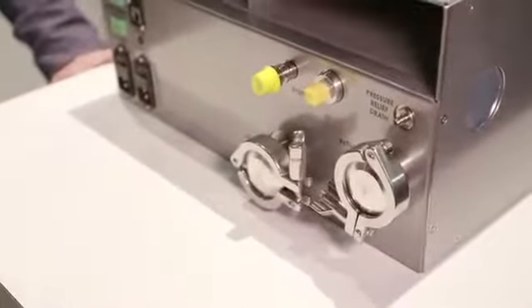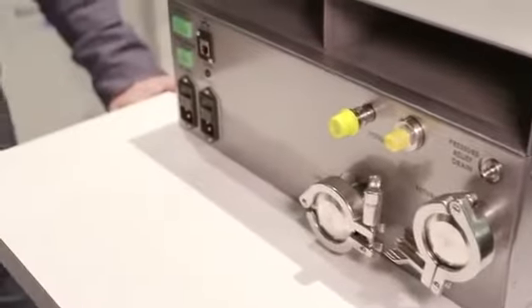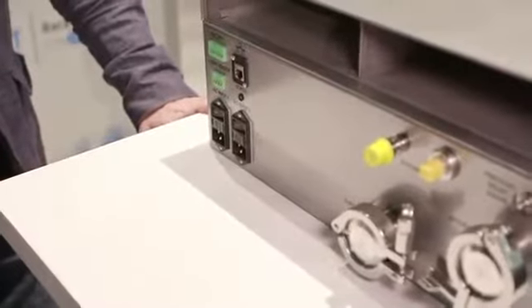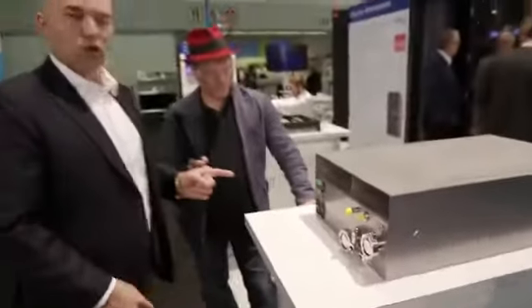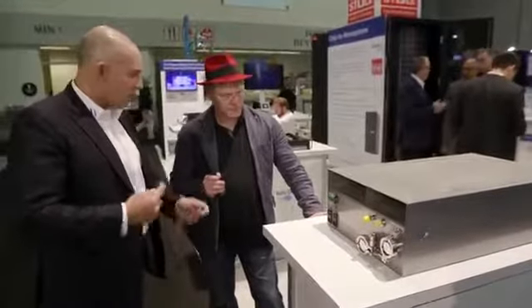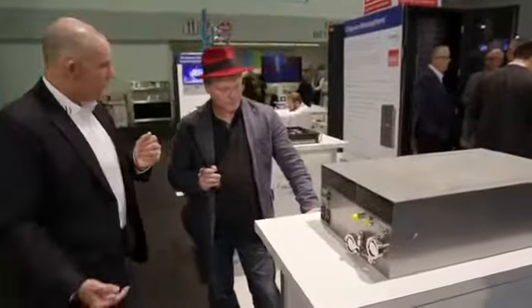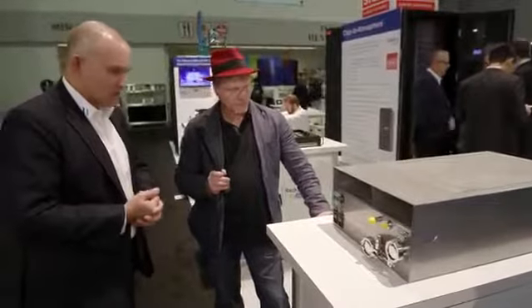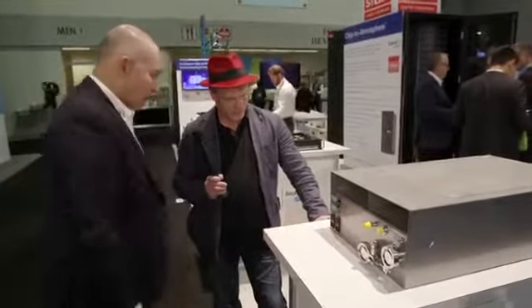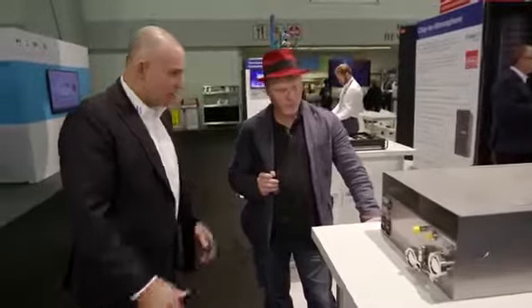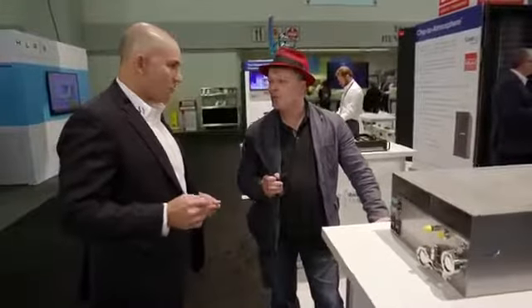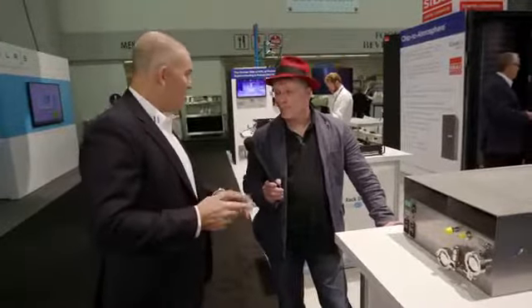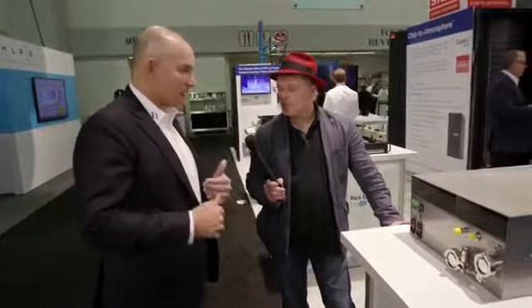We've got network status and a facility zone sensor, so you can do external leak sensing if you wrap leak sense cable around the manifolds. We've also got dual redundant power supplies, with full reporting capabilities so you can tell if a fan were to fail or if there were issues like flow or pressure.